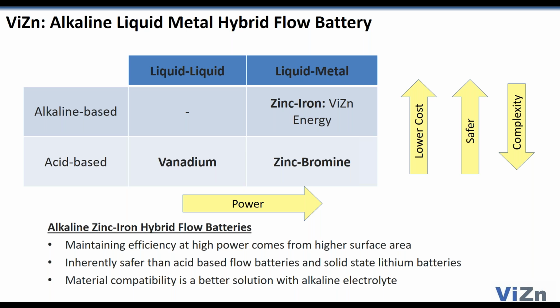Zinc bromine is another acid system. It also uses zinc and is what's referred to as a hybrid or liquid metal battery—on one side you plate zinc up as a metallic deposit on an anode plate, and on the other half, the cathode reaction is a liquid system. That's the same as the ViZn battery; zinc bromine does it in acid, ViZn does it in alkaline. Because we're alkaline, we can't dissolve quite as much material, so we have somewhat lower energy density, but we're much safer and much less corrosive. So those are the three basic flow battery technologies out there.